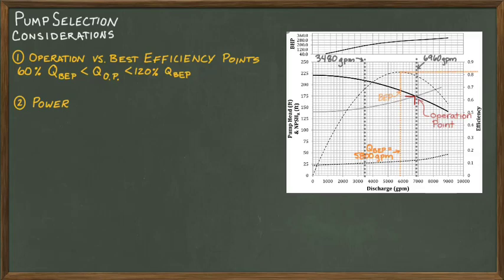When we talk about efficiency, what we are talking about is the difference between the power applied to the pump shaft compared with the power observed in the fluid. In other words, if we set a flow meter immediately downstream of the pump where we will be able to measure the flow rate and the pressure head generated by the pump, if we multiply that by the unit weight of the water, gamma, then we can compute the power in the fluid.